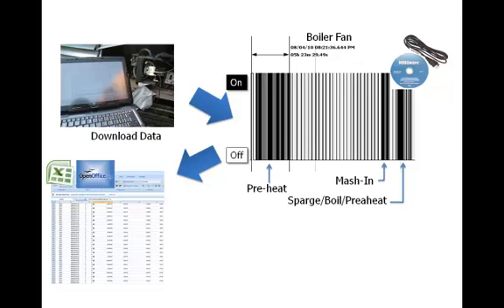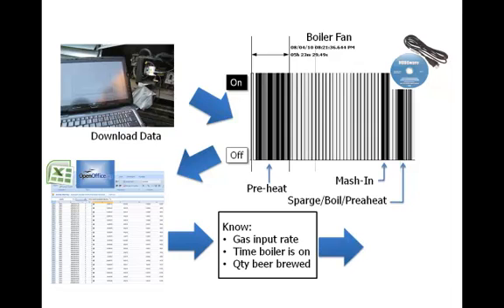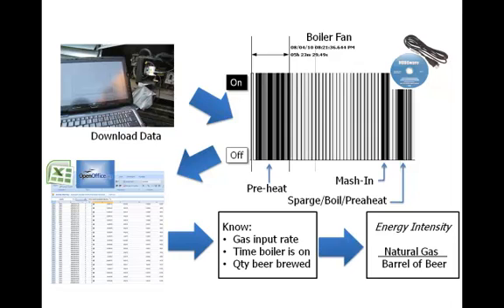After some data manipulation, which I'll go into in further detail later in this presentation, we were able to come up with some important pieces of information. We know the gas input rate because it's stamped on the side of the boiler. Looking at the data, we know the time that the boiler is on. We know how much beer is brewed based on production logs from the brewery. All this information can be combined to give us a very useful metric called the energy intensity — the amount of natural gas used for every barrel of beer produced.